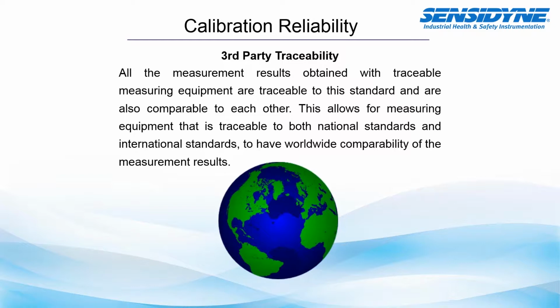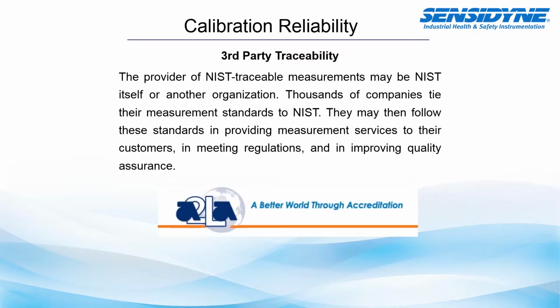Sometimes we actually ship equipment worldwide for use, and we want to make sure that when we put in a unit of measurement, it is a traceable unit that will be both understood and accepted from national organizations worldwide. The provider of the NIST traceable measurements may be NIST itself or another organization. As I mentioned, manufacturers who manufacture the calibrators and the air sampling equipment will use these traceable measurements to the NIST standard. A lot of times they have a primary set of calibration devices that they'll then use to calibrate their other production equipment. This traceability can be audited by third-party agencies as well.